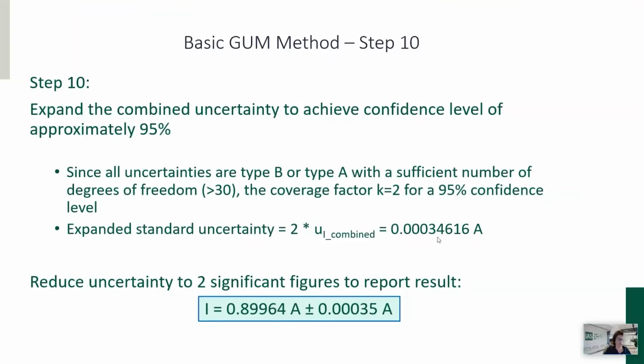If we put our result plus or minus the uncertainty, and give the uncertainty at a 95% confidence level, then you could say you're 95% confident that the true value of your result lies somewhere between 0.89964 amps plus or minus 0.00035 amps. So that is your final result.